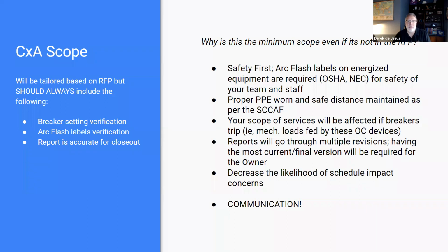So you need to make sure you're wearing and keeping safe distance away such that you can do your job safely. Because, as we just mentioned, all of your scope is fed from electrical equipment. So all of those sources should have an arc flash label and should be properly coordinated via that SCCAF report. So the breaker settings will be verified, and we'll talk about how that's done in a little bit. Arc flash labels are applied, and we'll talk about what happens if those get changed, because those reports likely will go through multiple revisions on a project. If those are revised, new settings will be provided, as well as new labels will need to be affixed.